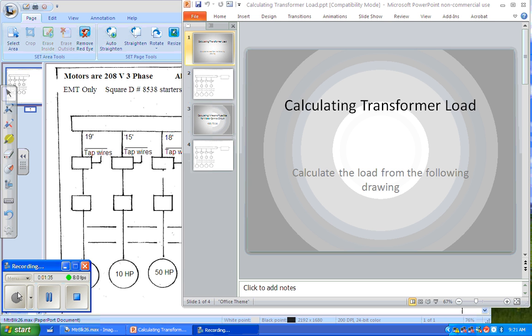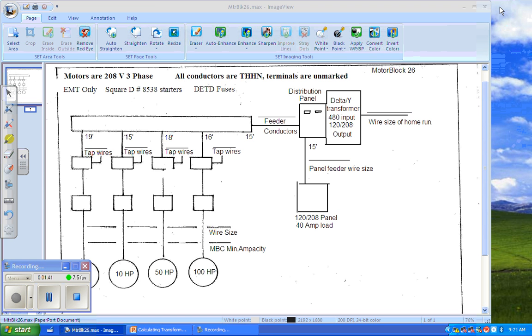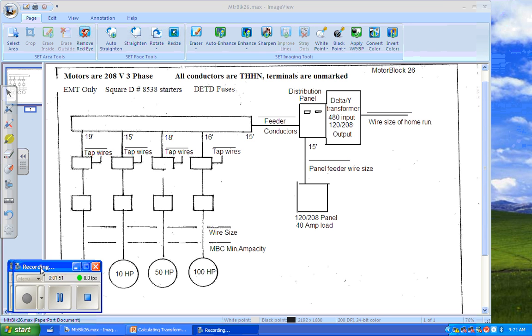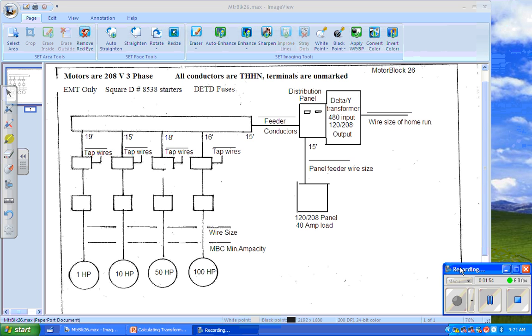Okay, so let's look at a motor block we're going to put in. Let me move the recording block. We have just 4 motors in this thing, and we can see their horsepower, right? So let's look up in 430.250, these are 3-phase. They're 208 3-phase motors. So we're going to look up their full load amperage because we need to know, right? And we're going to do it just like we would any other calculation.